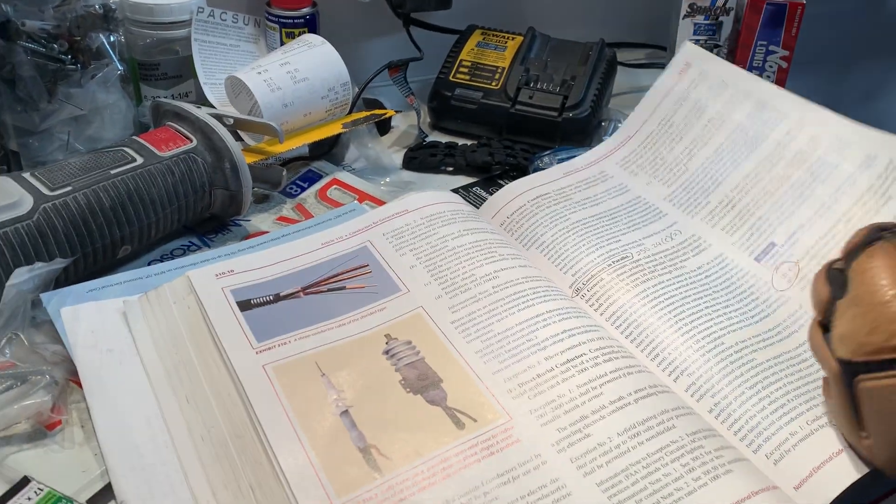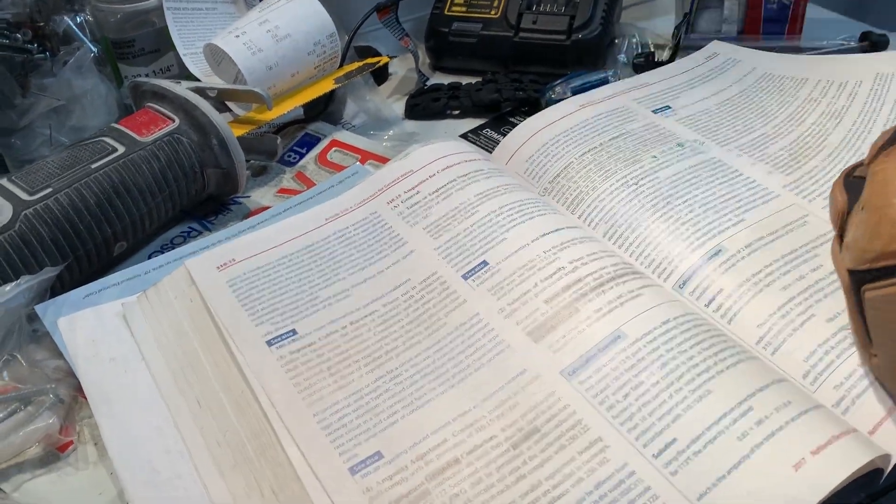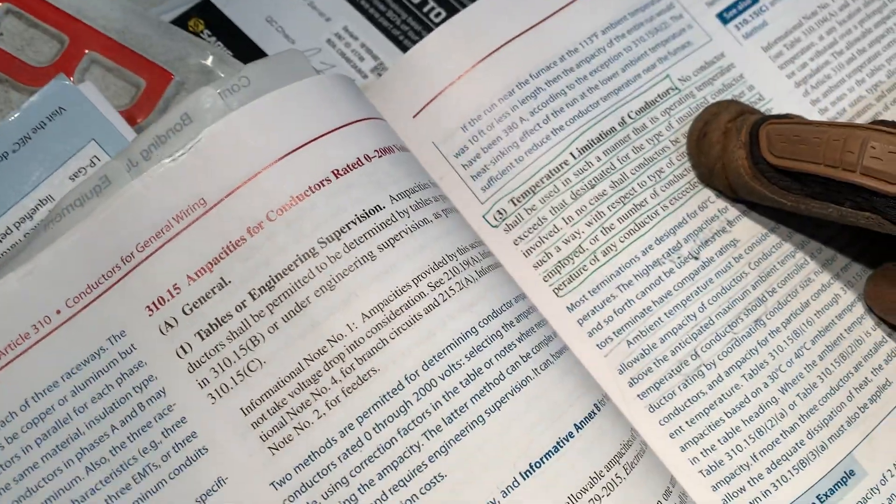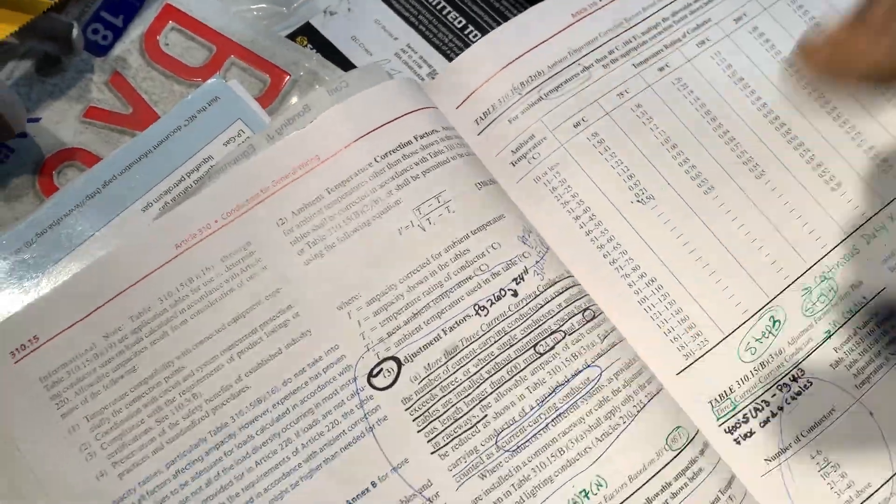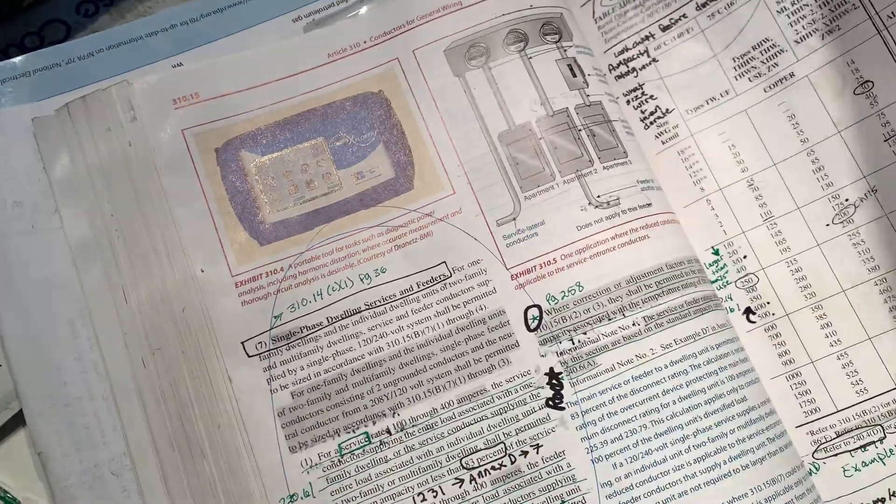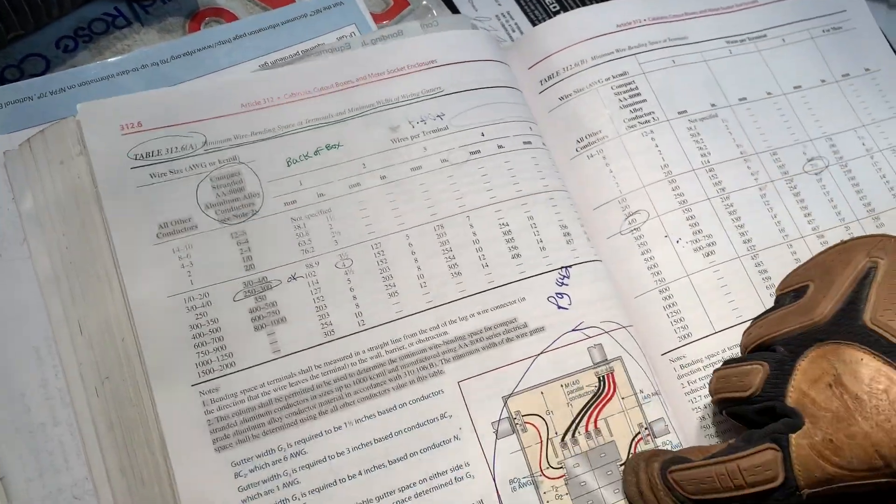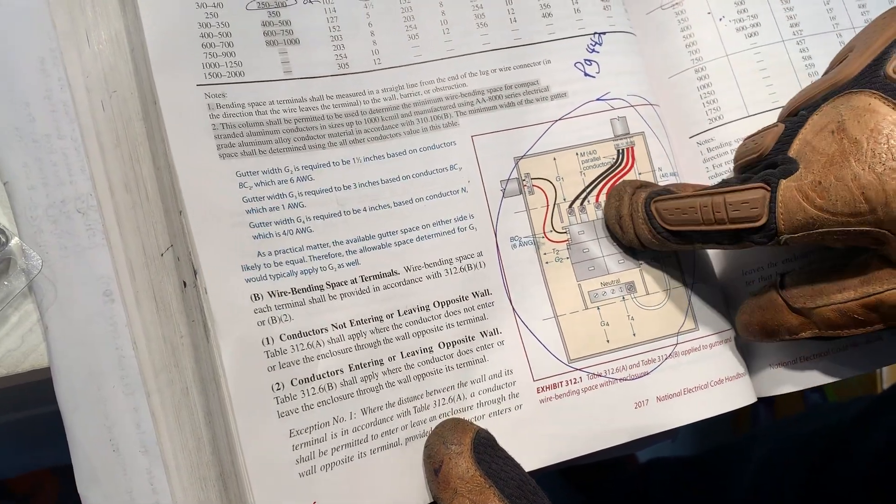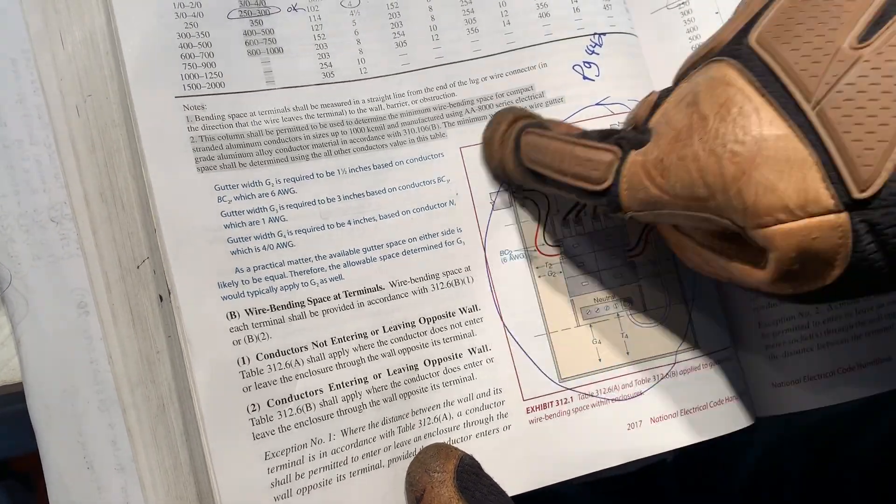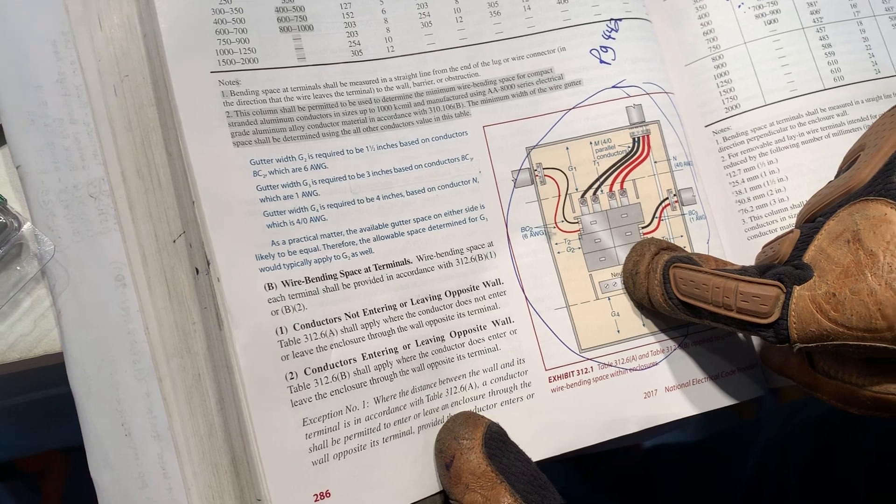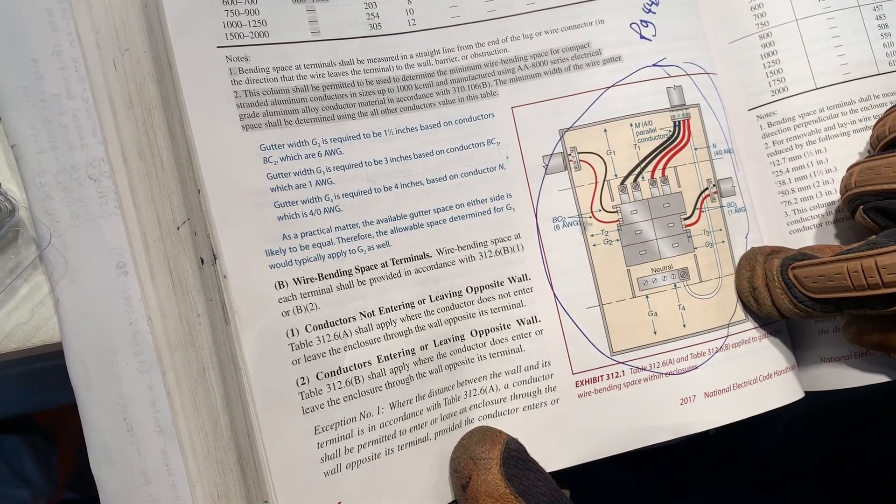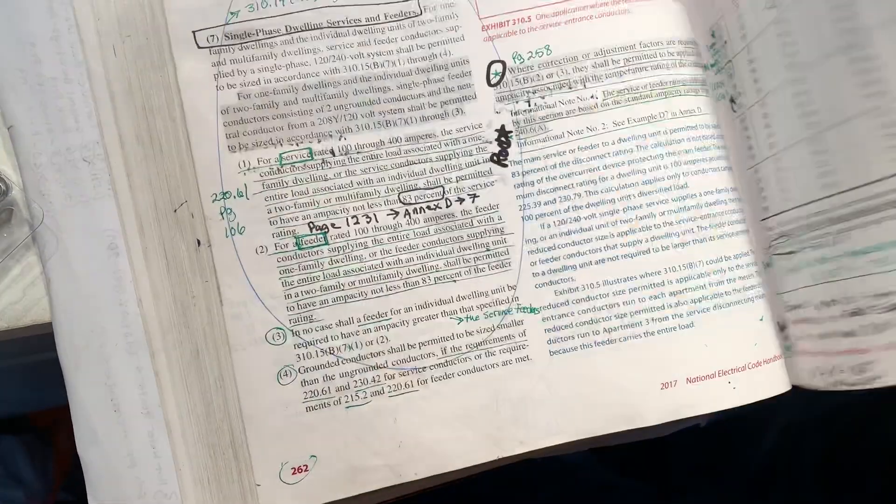You also have to pay attention to temperature limitations of your conductors. But there was a really cool picture to show you something. I think it was 312. Right here. When you're bending wires into a panel, you cannot just bend them and loop them. You can do a gentle loop, but the way they had them bent in there, I couldn't even get the panel cover to shut. So that would be code number violation 14, and that's in 312.6.